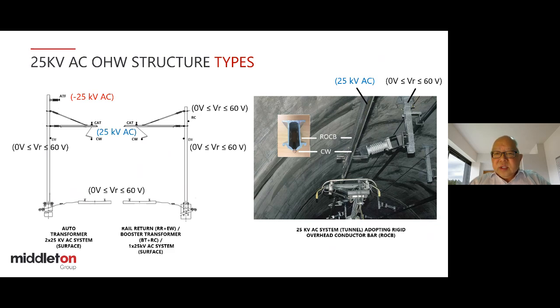So it uses an aluminium extrusion, which is hollow in the middle, and the hard-drawn copper contact wire is clipped onto the bottom of it. Your pantograph is actually making contact with the contact wire, not the aluminium. So you can see the insulator between the ROCB and the support, and there's also an earth wire running along as well.